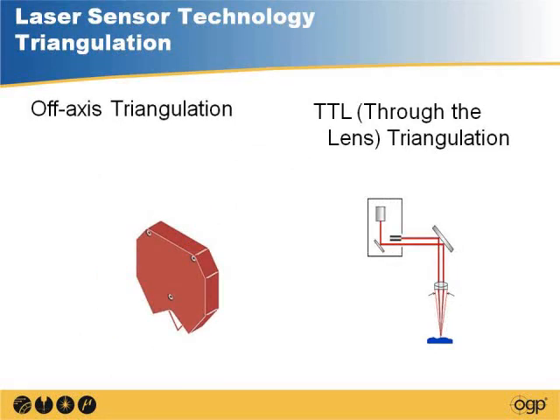There are a couple of different ways that triangulation is applied. There is off-axis triangulation. We have this standalone laser head. That red box there has an internal laser, so this can be added onto a measurement system, or sometimes they're standalone by themselves, just scanning very high accuracy traces or very small features, and sometimes they're incorporated into an online system for online measurement.